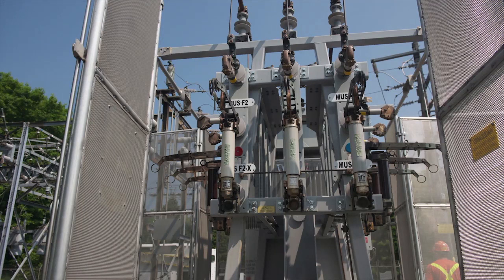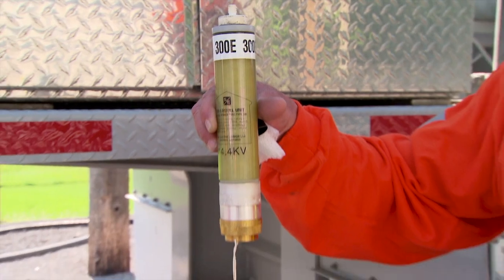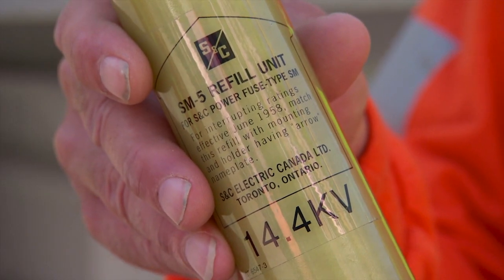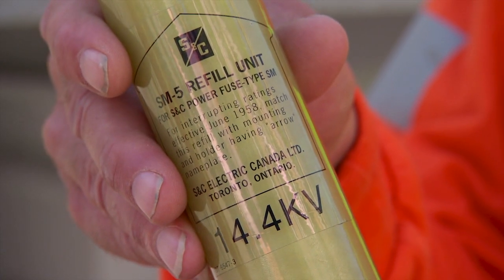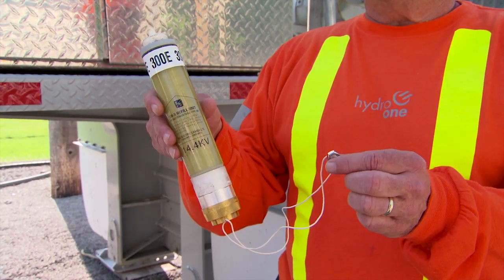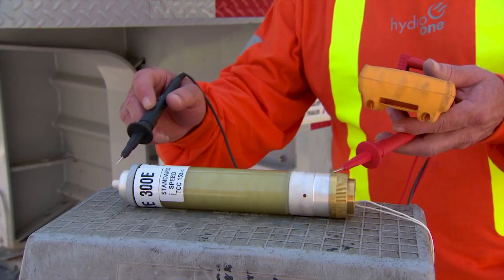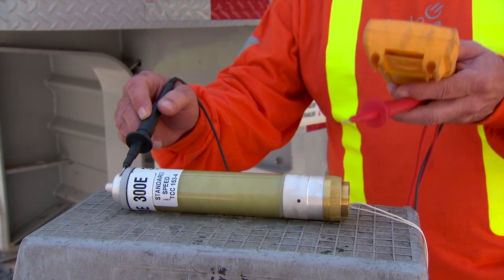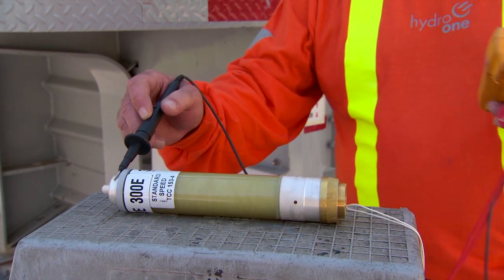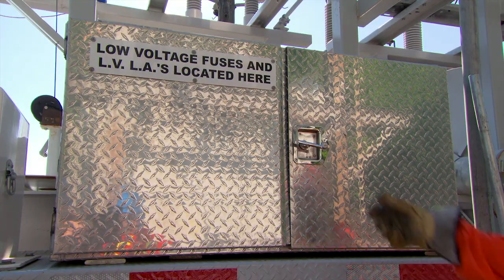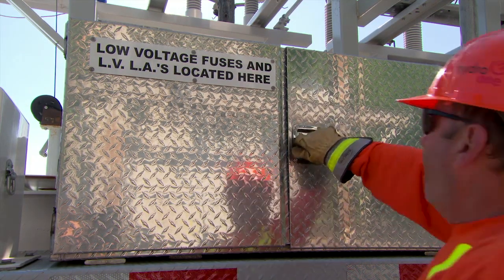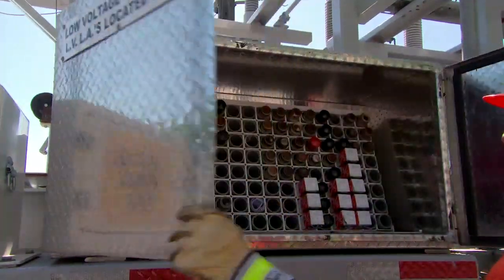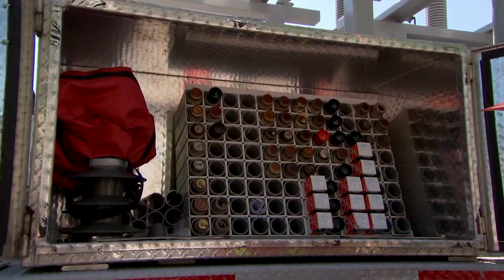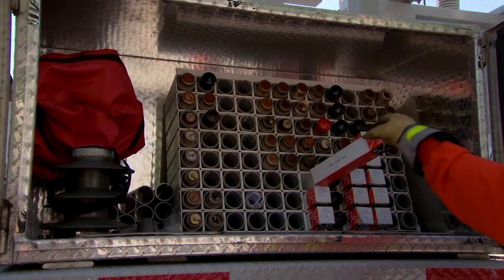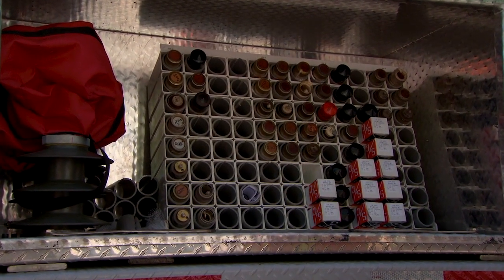Mobiles without reclosers will be equipped with 9 low-voltage fuses, 3 for each feeder. These fuses provide feeder protection. The required fuse ratings can be determined using Appendix C in Hydro One's document SP 1609 and SP 1610. The fuse elements are configured on site while preparing the mobile for installation. Typically, 3 spare fuses are also prepared in case of an emergency situation.